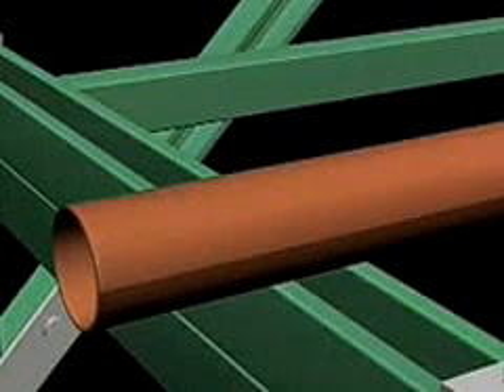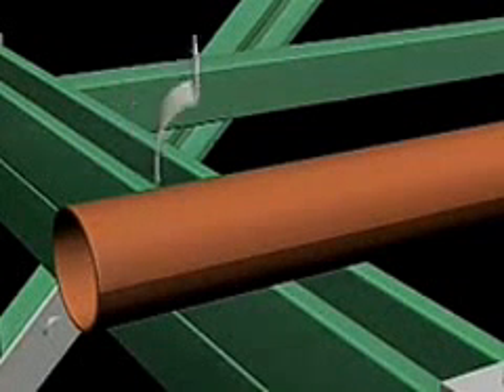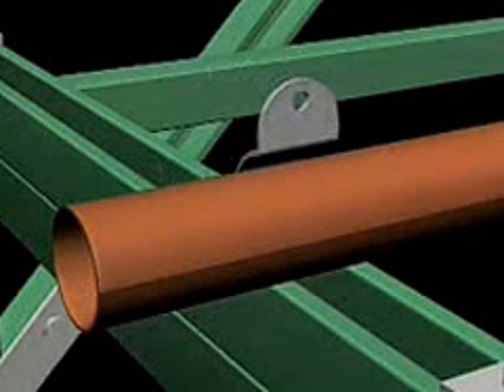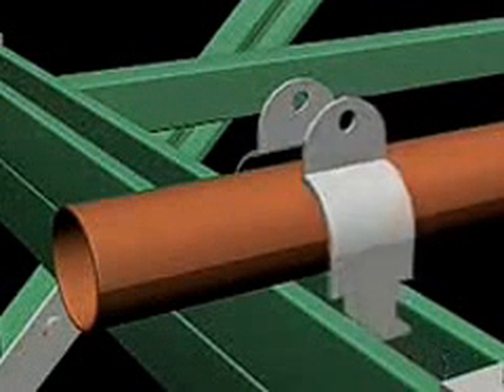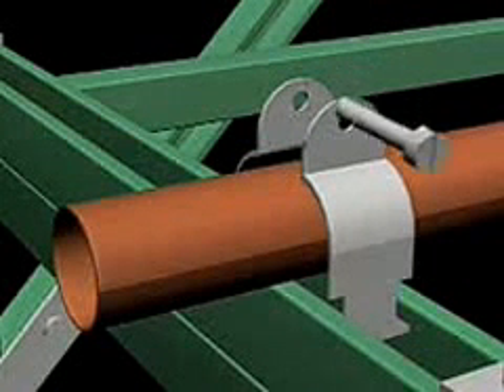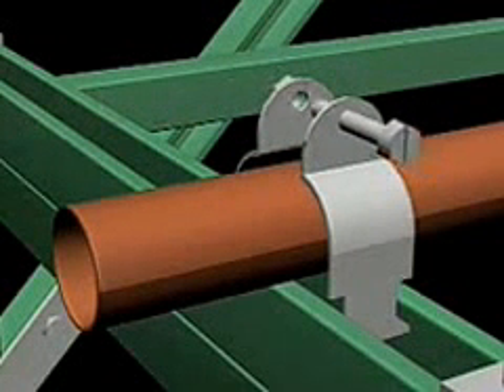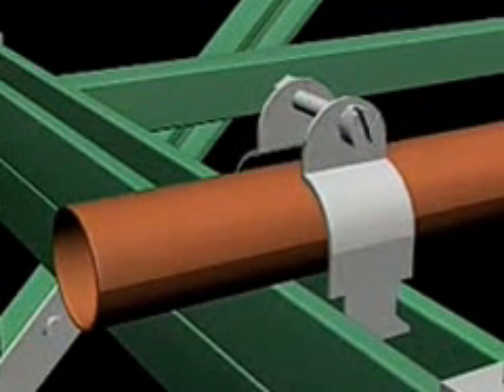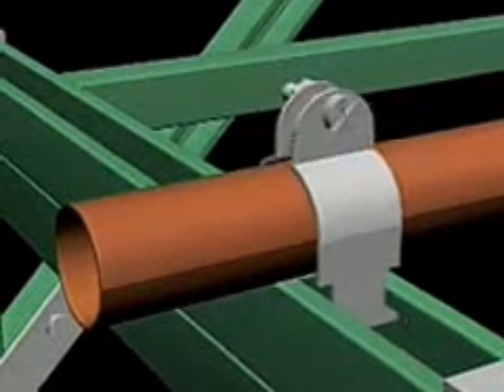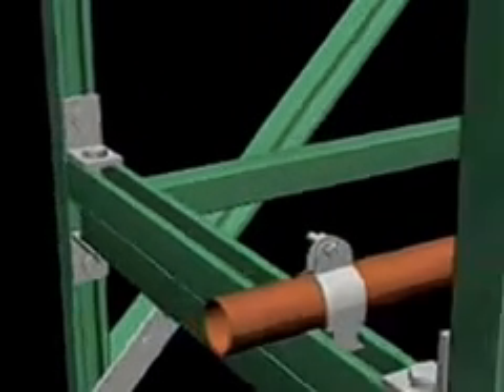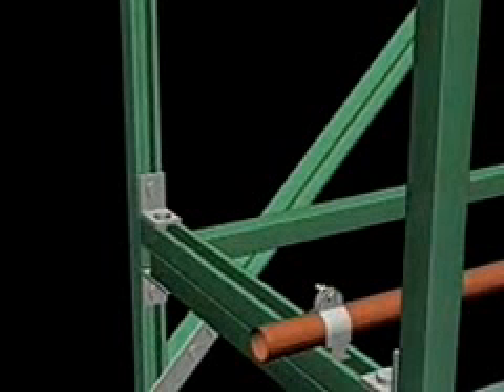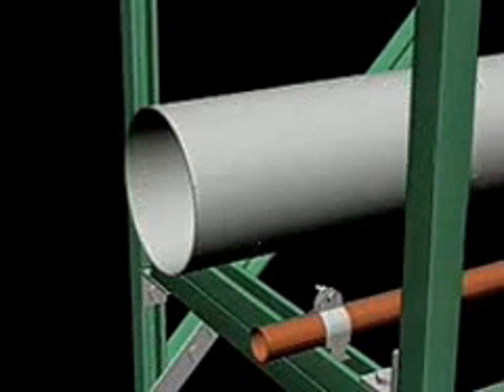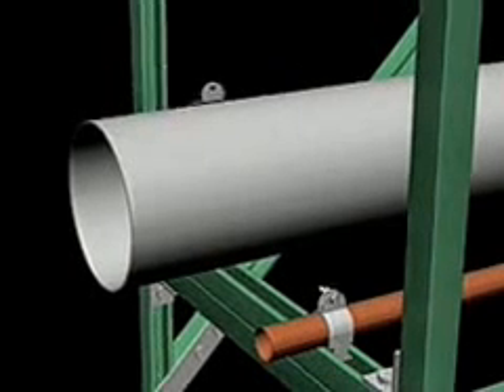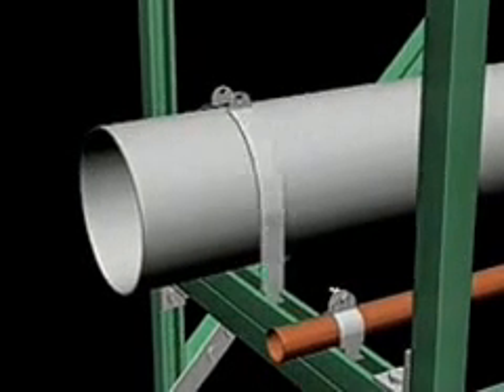To install pipe, simply position pipe on the channel support and insert the 2 halves of a pipe clamp. The tabs of the clamp hook easily to the inturned edge of the channel and can be inserted anywhere along the channel. Now simply insert the clamp bolt through the holes in the top of the clamp and tighten with the nut provided. You will note that the curved straps of the clamp conform to the outside diameter of the pipe to provide a snug fit. The process for installing conduit is exactly the same.